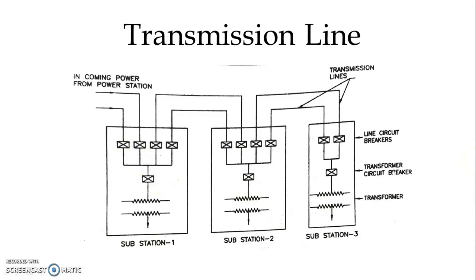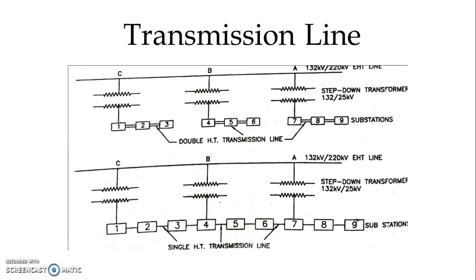We have four line circuit breakers, one transformer circuit breaker, and one transformer to step down the voltage. The extra high-tension transmission line is tapped from suitable points and feeds power to the substation. The voltage is stepped down at the substation, and substations are fed power through the double high-tension transmission line.